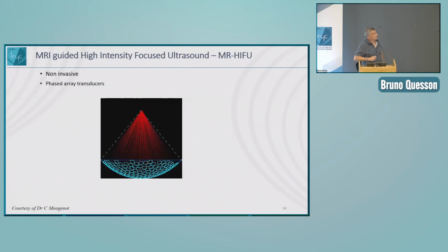So what you see in this cartoon is that you are able to concentrate the energy in different locations inside the tissue, and this is done using a specific emitter, which is not a single emitter, but is composed of an array of emitters. Changing the electrical phase of each signal that is sent to each individual element will modify the constructive interference between all the individual ultrasound fields generated by each emitter. And then using this, you can target deeper, closer, left, right, and in 3 directions.